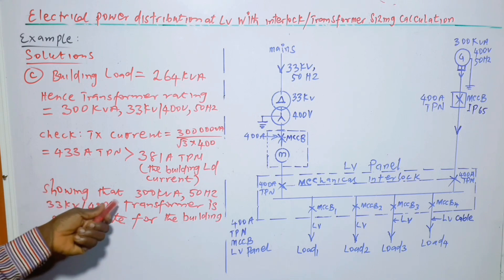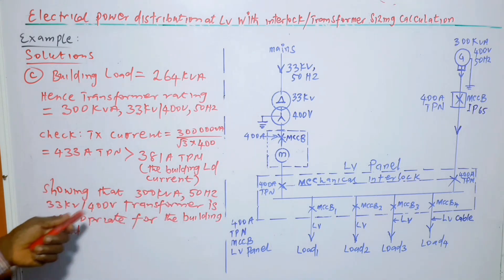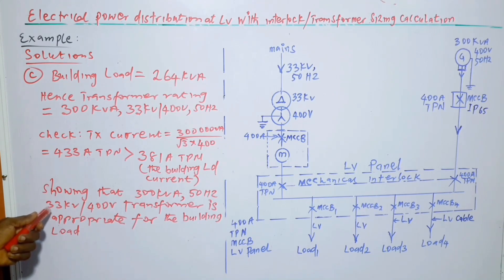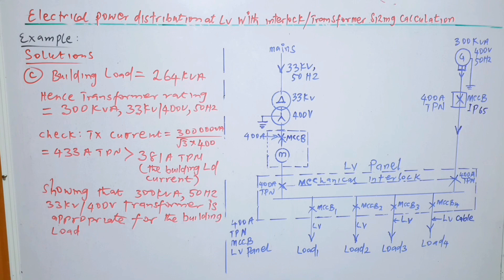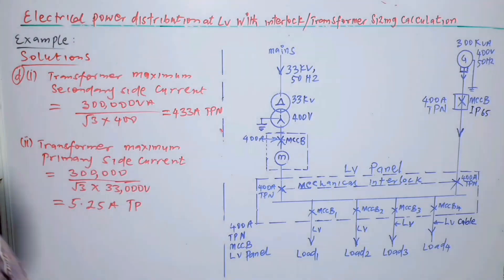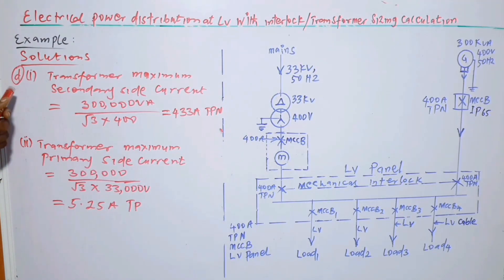So that is showing that 300 kVA at 50 hertz with 33 kV on the primary side and 400 volts on secondary side transformer is appropriate for the building load. And that is the answer to C part. One can move a step further by having the D part.